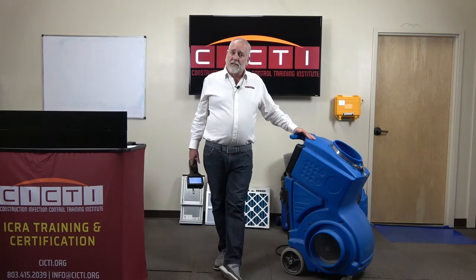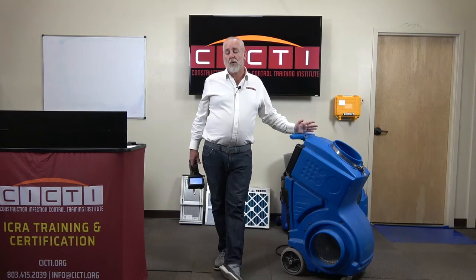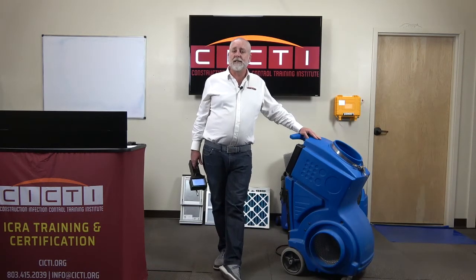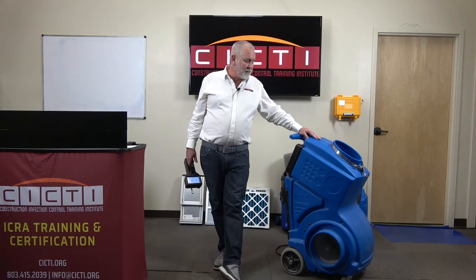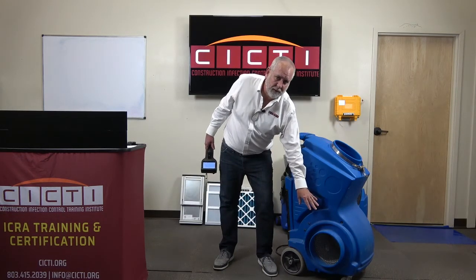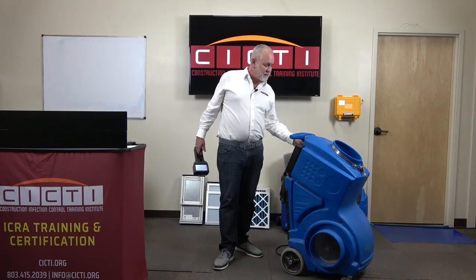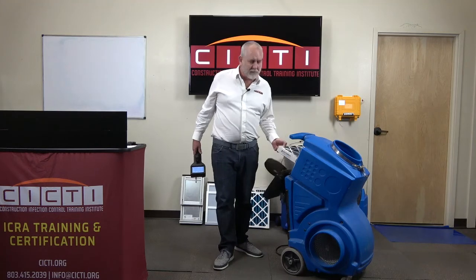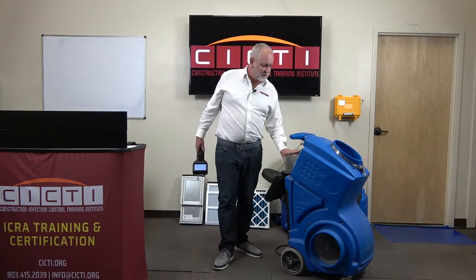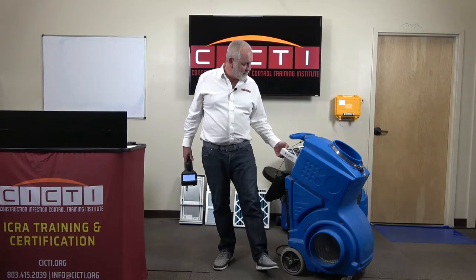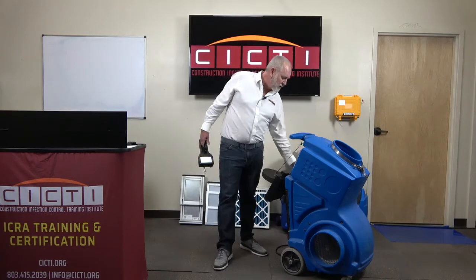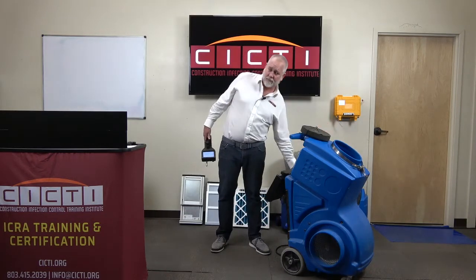We want to test these devices at least annually, or no more than a full year between testing, or any time that the HEPA filter is replaced. Not the pre-filters. In this device, we've got pre-filters up high. We don't need to retest when we change these filters. These filters are really just to lengthen the lifespan of that high dollar filter. That's really the only filter that matters in this system. These filters up front, with the exception of the carbon filter, are pretty much just for the owner of the device to save them money, so they don't have to change the high dollar filter down there in the bottom.